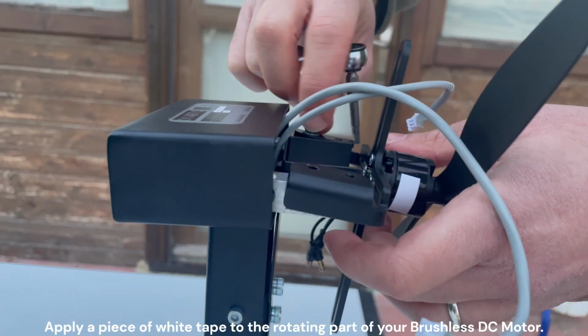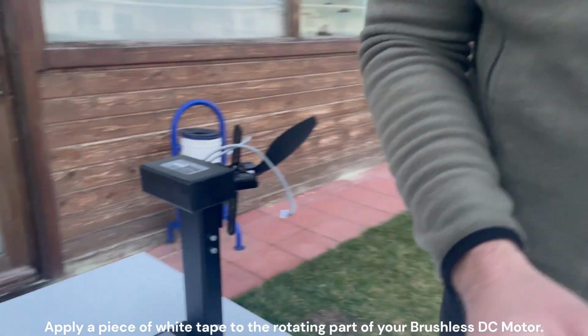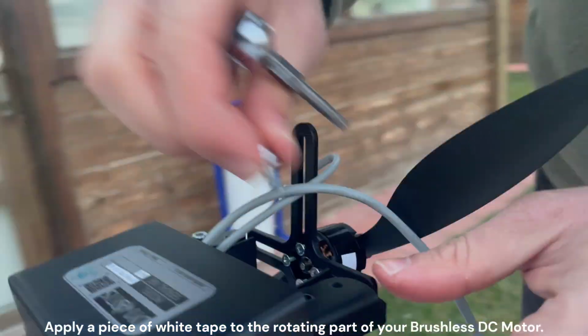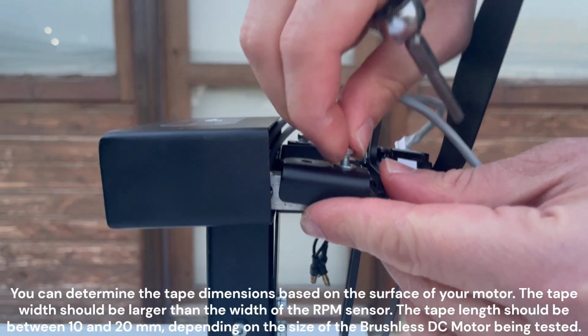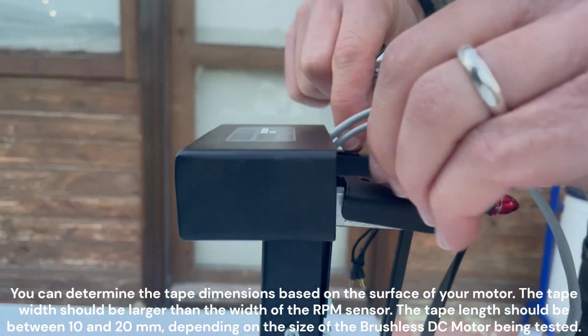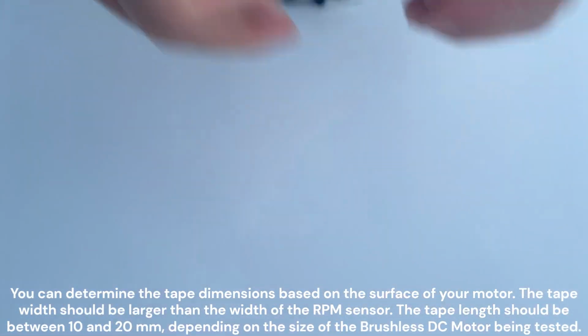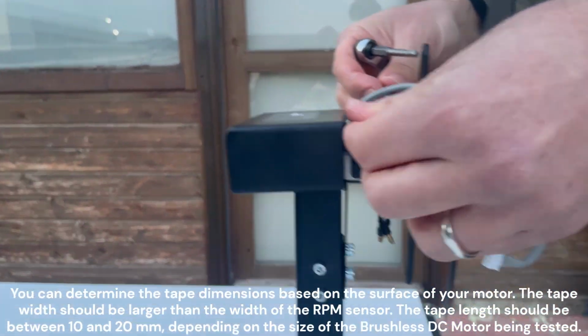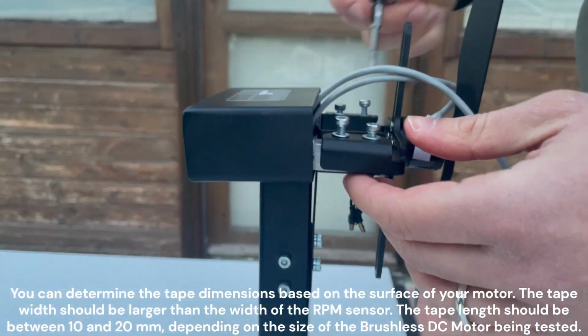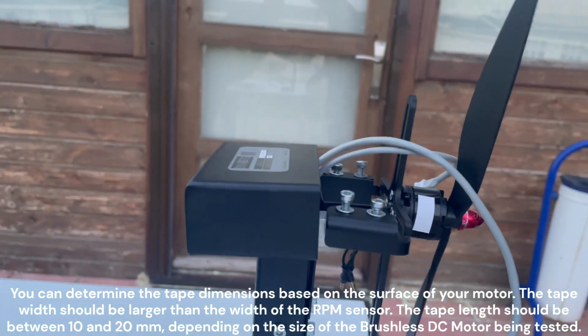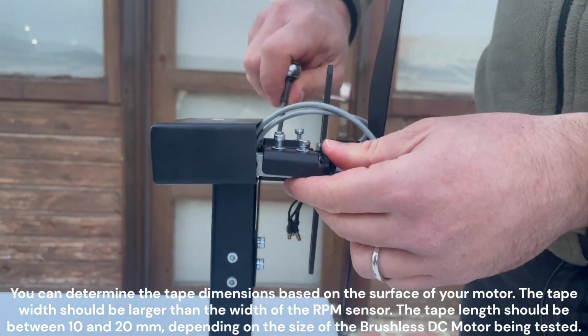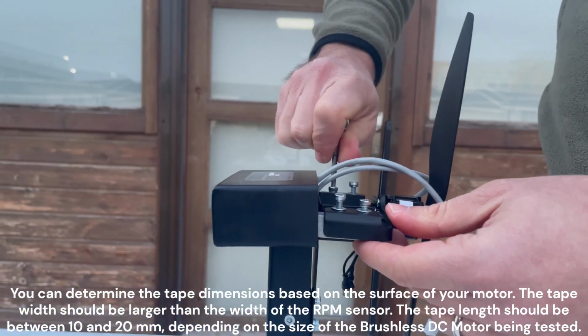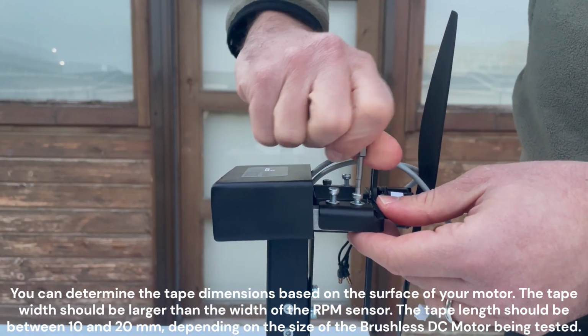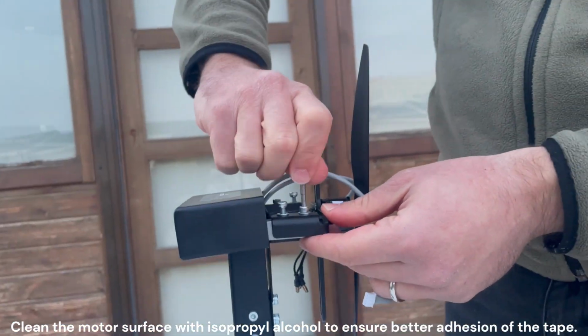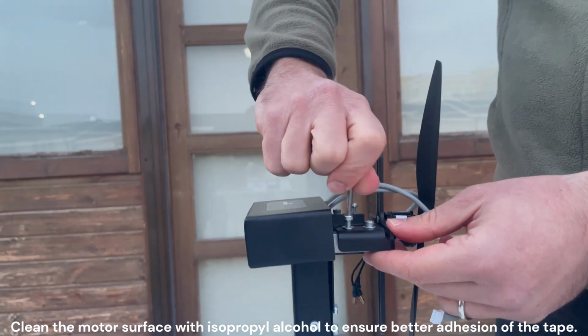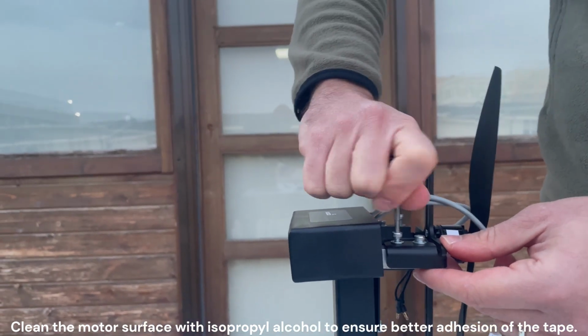Apply a piece of white tape to the rotating part of your brushless DC motor. You can determine the tape dimensions based on the surface of your motor. The tape width should be larger than the width of the RPM sensor. The tape length should be between 10 and 20 mm, depending on the size of the brushless DC motor being tested. Clean the motor surface with isopropyl alcohol to ensure better adhesion of the tape.